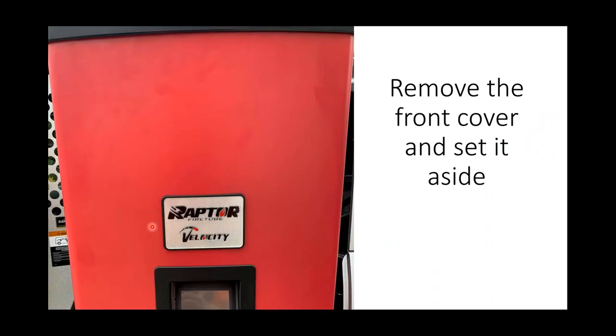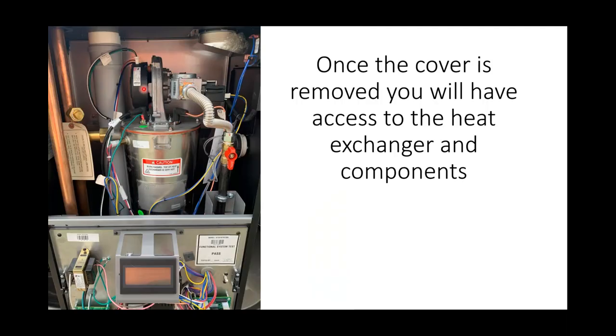So, getting into cleaning and servicing the unit, the first thing we're going to want to do is remove the front cover and set it aside. There's a handle right up in here, and the cover just pushes on. Grab it, give it a nice firm pull towards you, and the front cover will come completely off. Once the front cover's off, it gives you complete access to the heat exchanger. Here goes your heat exchanger right in here, your gas valve, the factory supplied gas cock to turn the gas lines off, your blower assembly, and all your high and low voltage connections are going to be down here at the base. But now you have full access to the heat exchanger and all of the components.